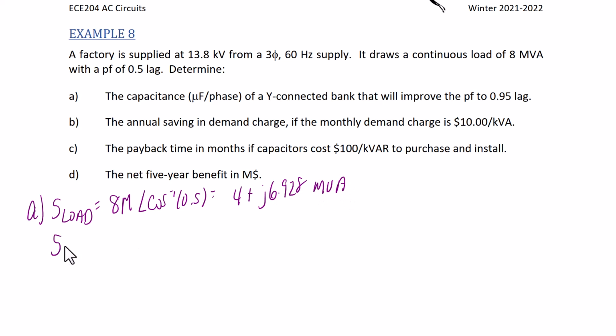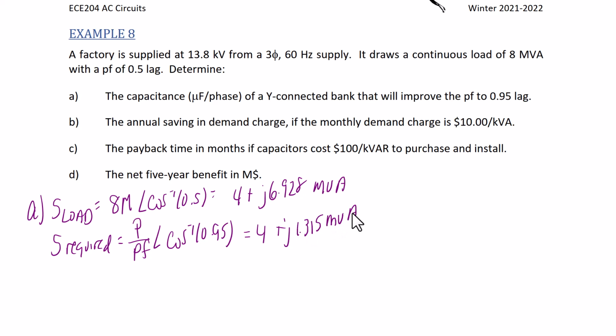Next, we need to find the required complex power to supply this power. So that's going to be the real power over the power factor with an angle of the arc cosine of 0.95. And that is going to be 4 plus j 1.315 MVA. So in order to find the required reactive power, we take the difference in the imaginary parts. So we're going to have 6.928 minus 1.315, which is 5.614 MVAR.